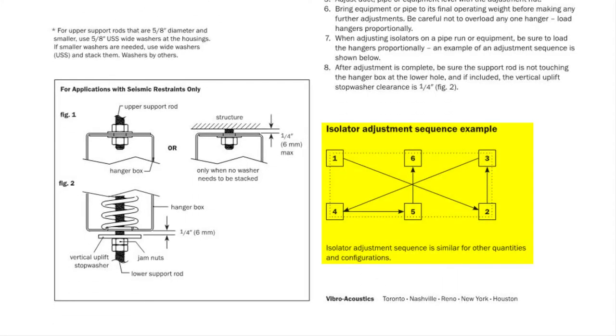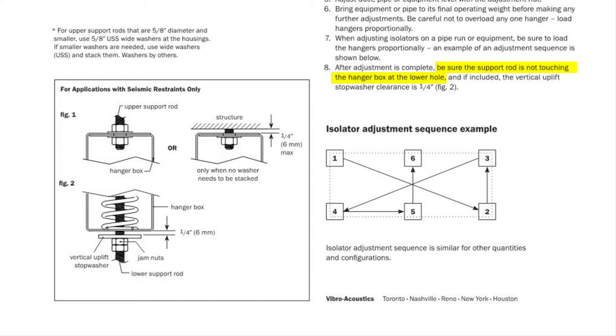And then an important final instruction is to ensure the lower support rod is not touching the edges of the hole in the bottom of the hanger box. Since this would create a vibration isolation short circuit, the vibration in the lower support rod coming from the equipment or pipe would transfer into the hanger box instead of going into the spring to be absorbed.